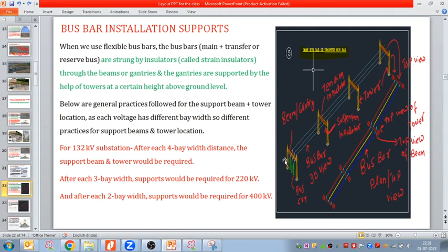This is how we provide support to the common busbar conductor stringing. This is what we discussed voltage wise. Let us see this example here. Again, this is my bus bar conductor, bus bar. Here I have the bus CVT, here I have the beam. This is my tension insulator beam, and here we have the suspension insulator. With the help of the tension and suspension insulators we are doing the stringing of this flexible conductor. This is my 3D view.